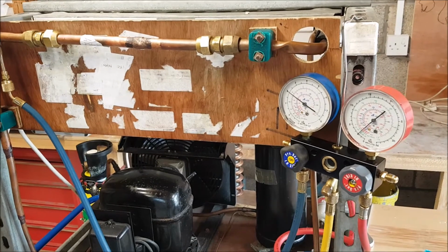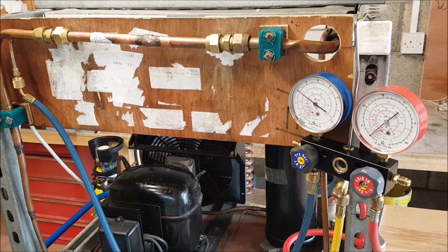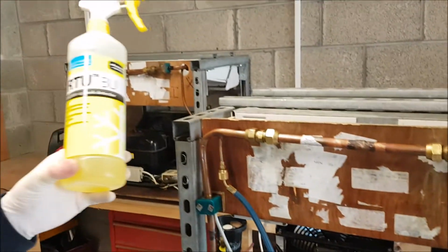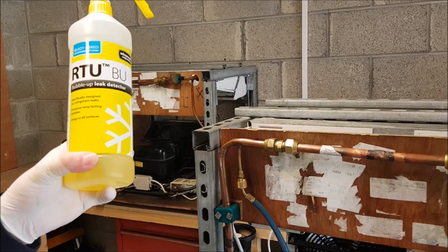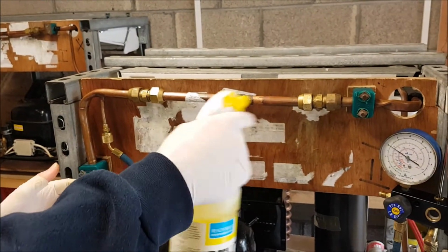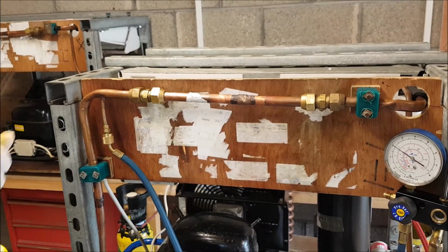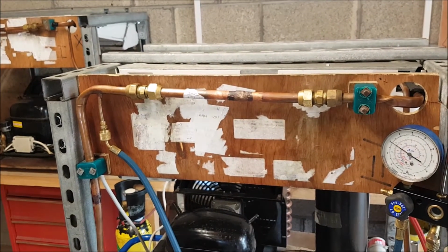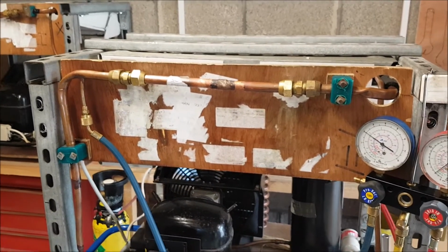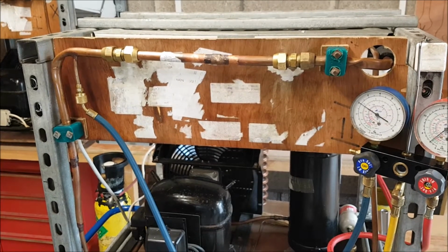And then the last thing that we can use is the bubble solution. I'll show you that in a later video, whereby you will go around with a typical bubble solution. There are different types from different manufacturers. You can buy bubble solutions, and this one is specifically designed for refrigerant. By spraying on the various different areas, which we'll show you in another video, such as flared joints, brazed joints, any kind of mechanical connections that are being made, if it starts to bubble up, that's a sign that there is nitrogen escaping from inside the system. That's where my leak is.